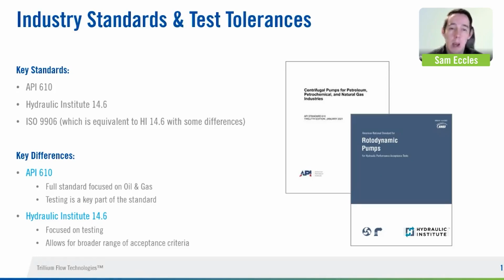The downside that comes with that is there's less flexibility, or you have to know where you need to deviate from the spec for higher energy, more complicated applications, where you need tighter test tolerances. Hydraulic Institute 14.6 is a testing standard. Now, the upside here is it has a much broader range of acceptance criteria.